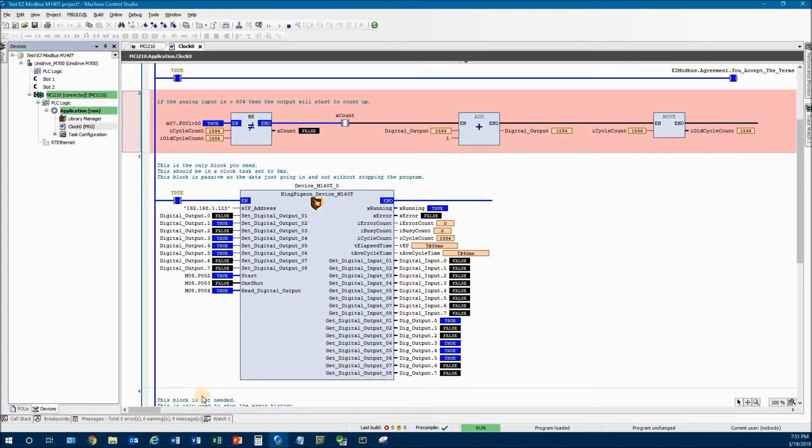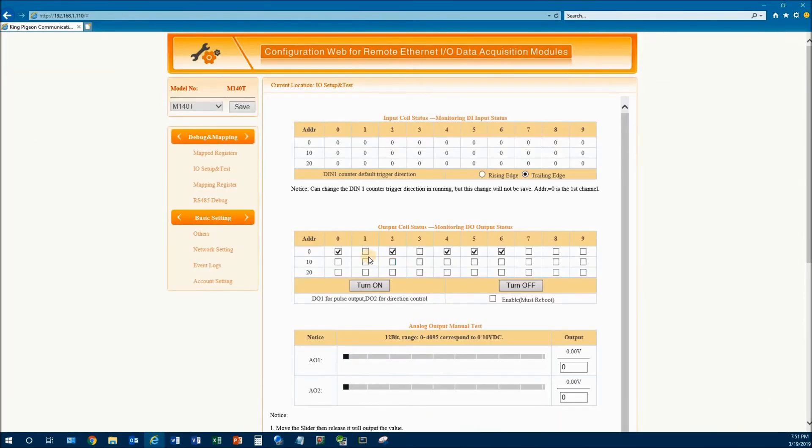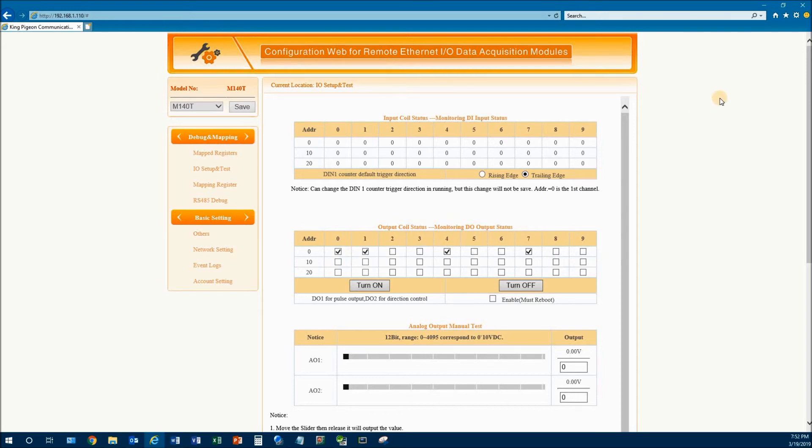And like I said about the web page, if we come back over to the web page, you can see that. So I just wanted to point this out. Again, this is a really handy page that a lot of bus couplers don't support. The only real downside to this bus coupler is it's not UL listed. It is CE listed, just not UL.